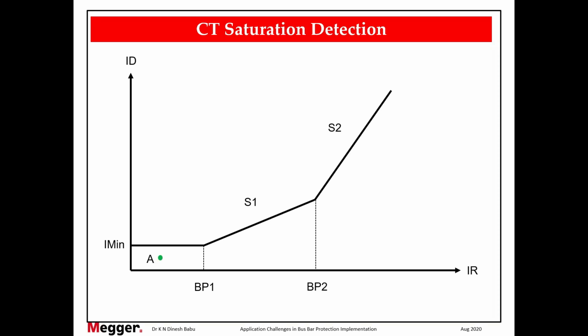Now, point number A plotted here. This point indicates that your system is healthy. There is no problem, no fault. The bus bar is in service. And why is there some differential current? This is your minimum supervision current, less than that because of your CT errors. So it is here. Now what happens? Suddenly a fault occurs. Let us assume it is an external fault. Now when an external fault occurs, use a differential view.